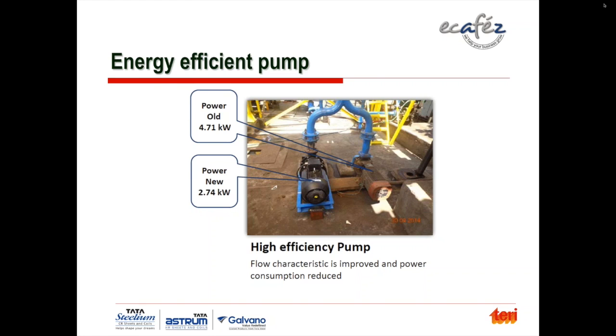It was replaced with a Grundfos pump which has a stainless steel impeller. Instead of 7.5 HP, we replaced it with a 5 HP pump. The power consumption reduced from 4.71 units to 2.74 units. Multiplying by 24 hours, 300 days a year, at 6 rupees per unit of electricity, the saving is about 85,000 rupees at an investment of 1 lakh rupees. The payback is about 14 months.